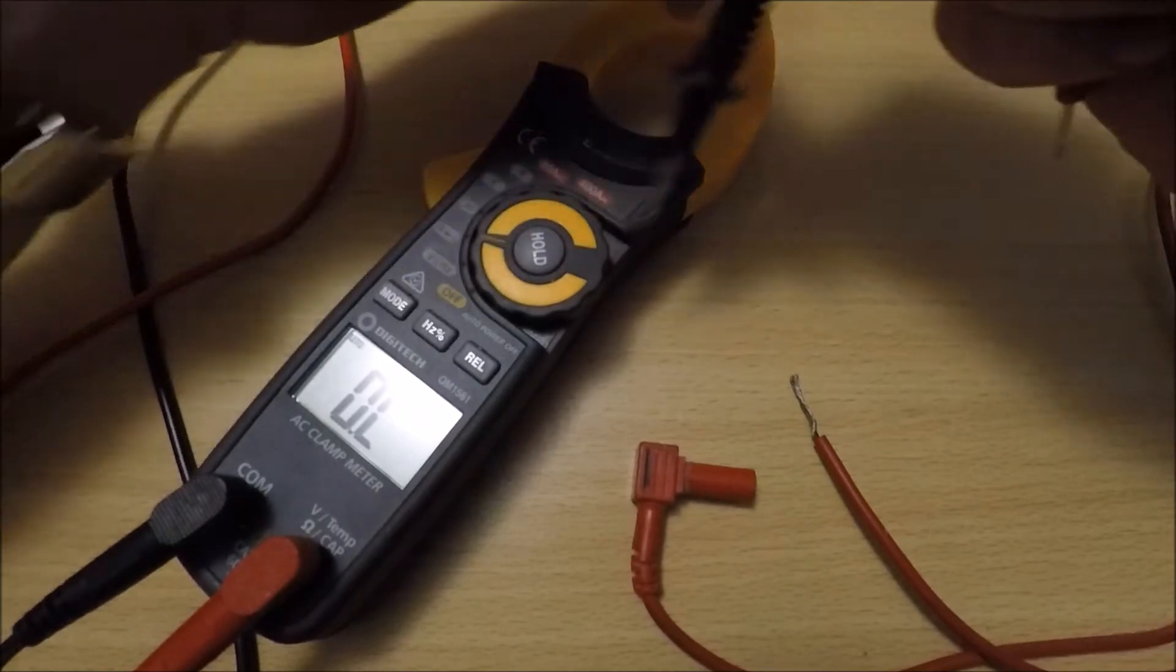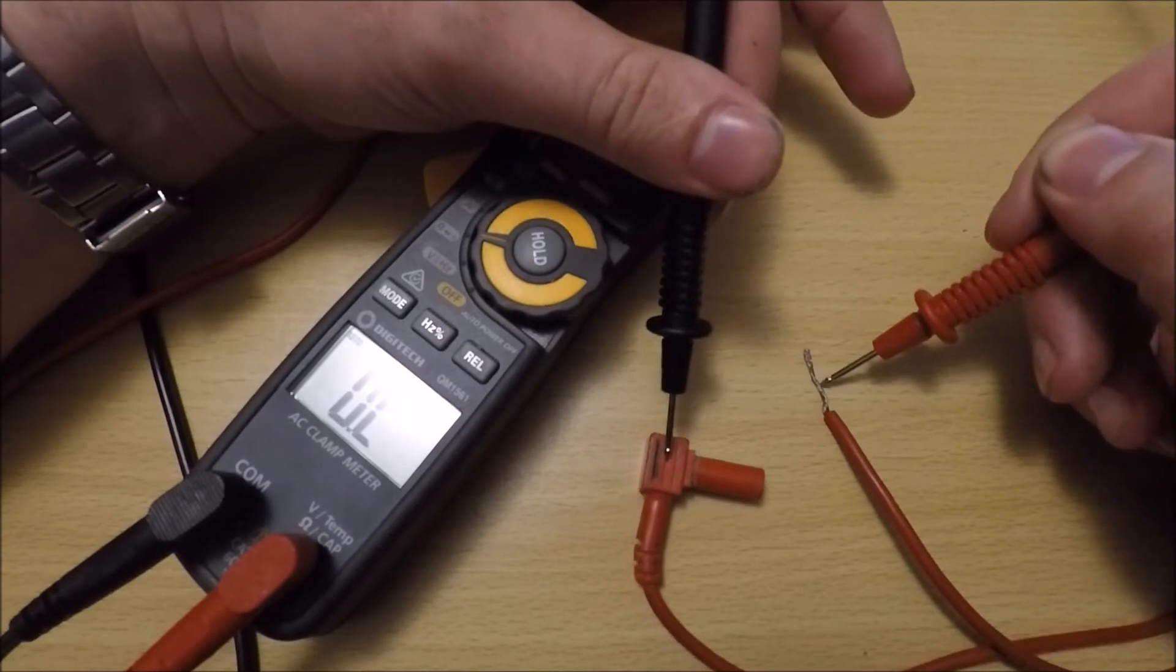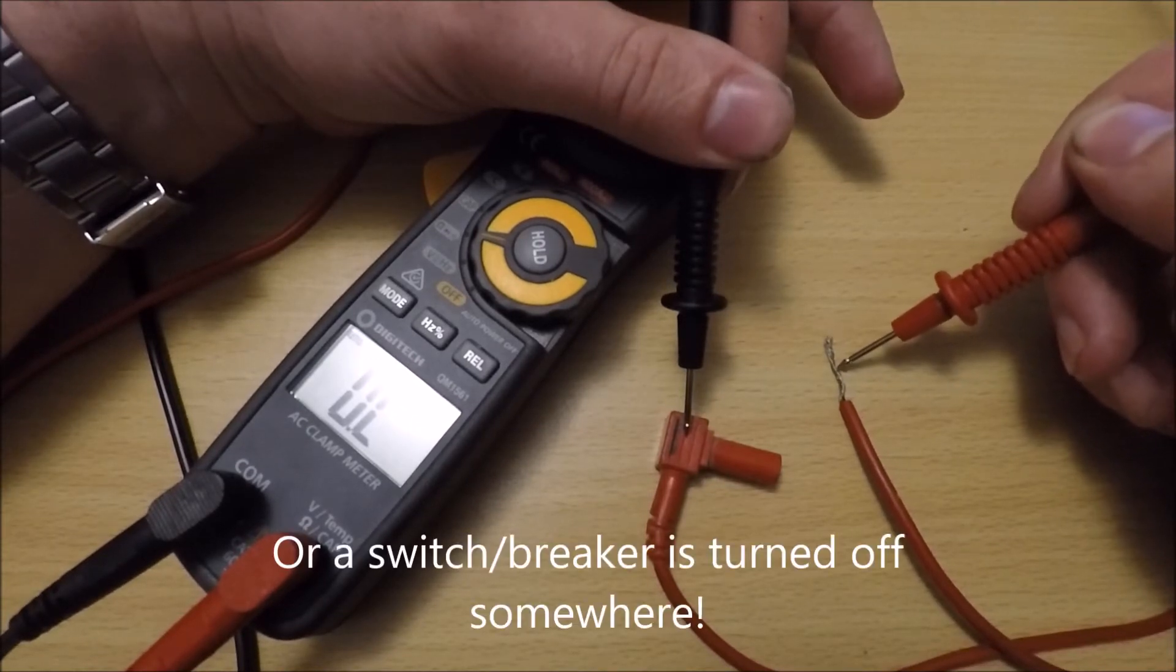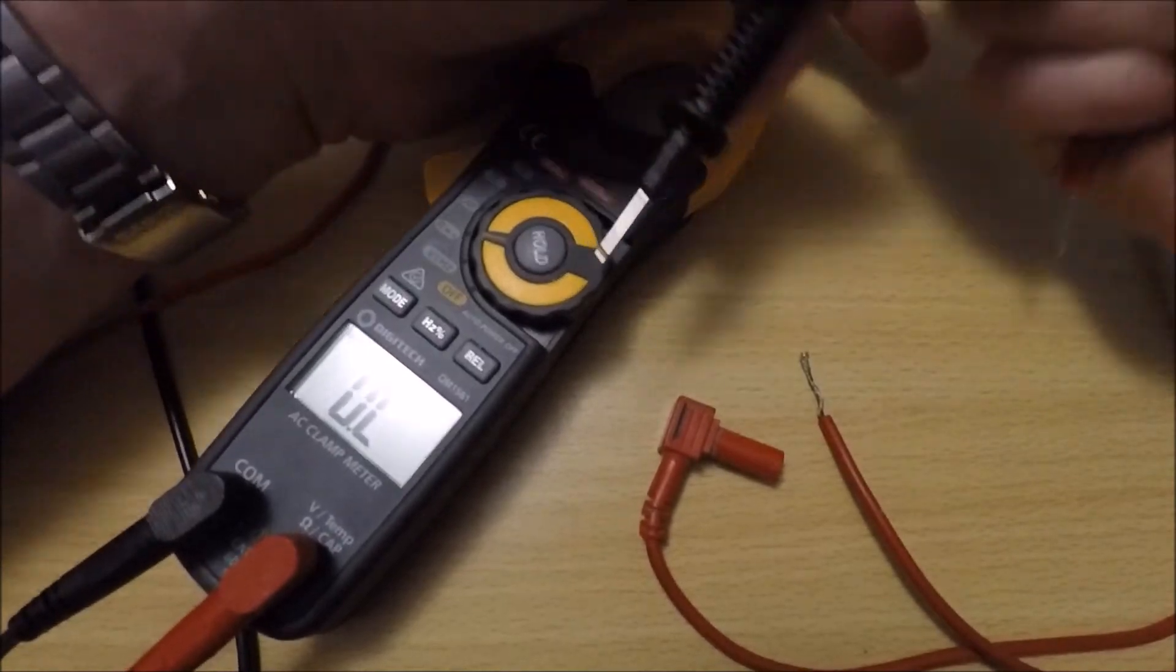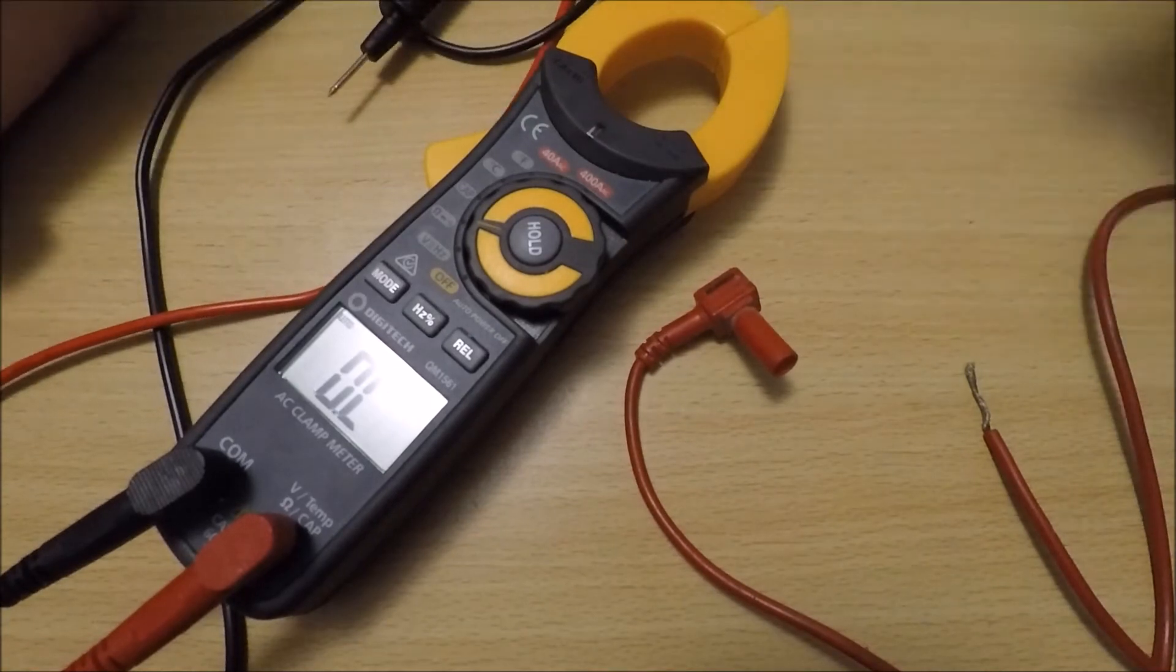We've got our two cable ends there, we've got our meter here. If we were to connect both the ends, let's say for instance I'm touching them both and it came up with OL open loop, it means the cable's broken. Maybe a rat's chewed it or someone's cut through it, maybe it's been cut through doing renovations. That might be why it's not working. If we've connected these for real, you want to see a resistance of close to zero. I should say an earth resistance no greater than 0.5 ohms. So this cable, we're on zero. The longer your cable, obviously the more resistance. That's why over distance we use thicker cables.